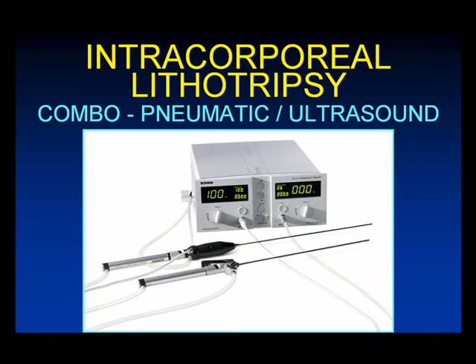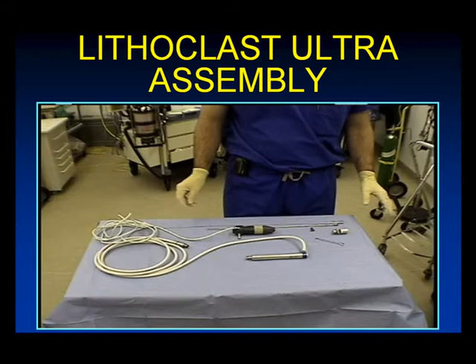So basically, it takes the concept of pneumatic and standard ultrasound. This is a standard ultrasound probe, and what we're doing is hooking up a connector, and then the pneumatic probe, if you will, goes through that connector, through the ultrasound handpiece, and then once we get the pneumatic probe in place, we can snap on a standard pneumatic handpiece. So here's the pneumatic handpiece. So basically, standard pneumatic all in one device, and this little knob will allow the pneumatic probe to come out just at the tip of the ultrasonic handpiece. And you can either step on the ultrasound alone, or you can step on the pneumatic alone, or as in most cases, we'll step on both pedals at the same time and get a combination of ultrasonic and pneumatic lithotripsy.